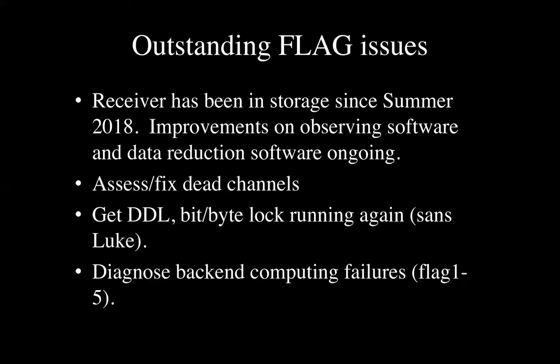Right now, the biggest problem is hopefully one that we can diagnose and solve, and that is that the back-end computers, FLAG 1 through 5, are all being fairly flaky right now and are not staying on. They've all been shut off for a couple months as we try to figure out what's wrong with that system. We have funds to repair at least some of them, depending on the exact failure, whether it's replacing power supplies or cards, but there are things that we still need to check out there. Obviously, without a functional front end or a functional back end, we can't observe. Hopefully, none of these are long-term showstoppers, but they're all things that need to be sorted out.